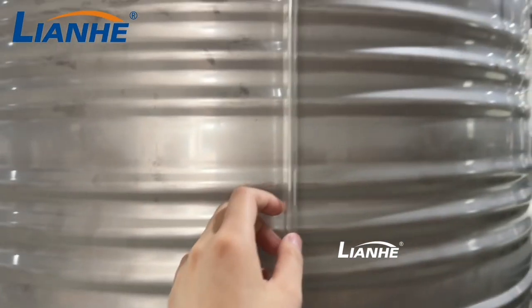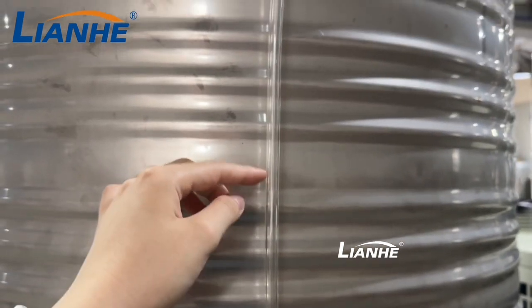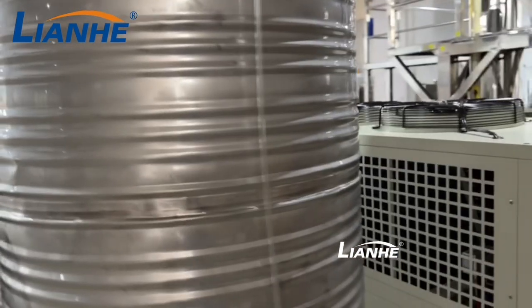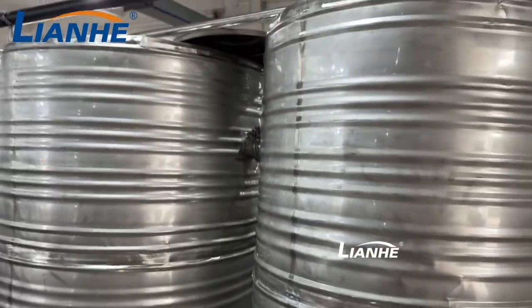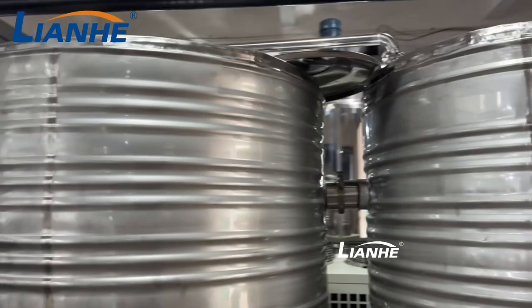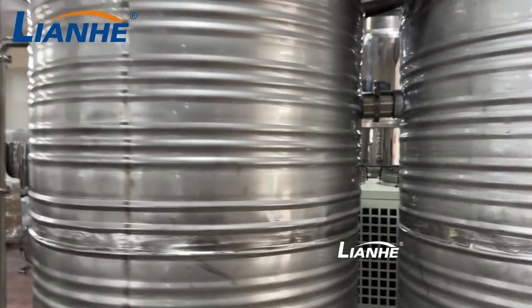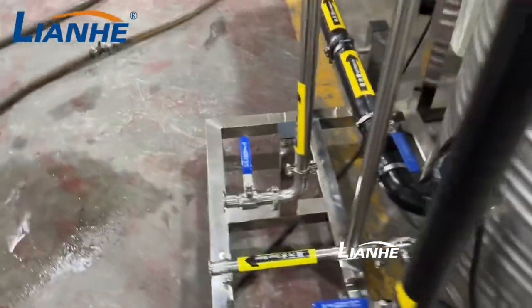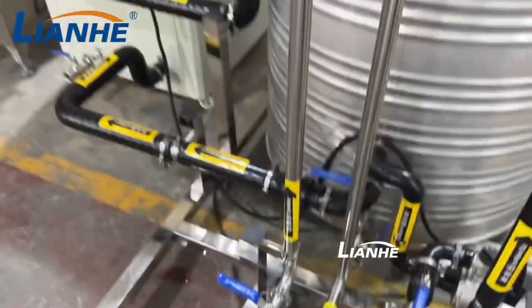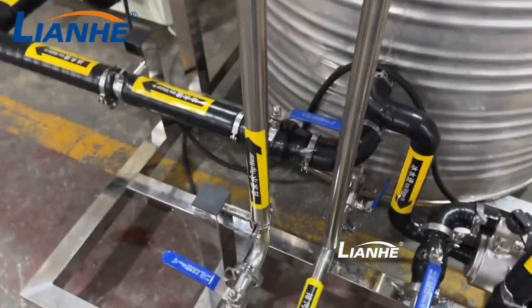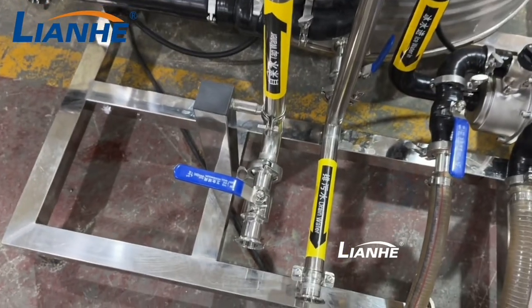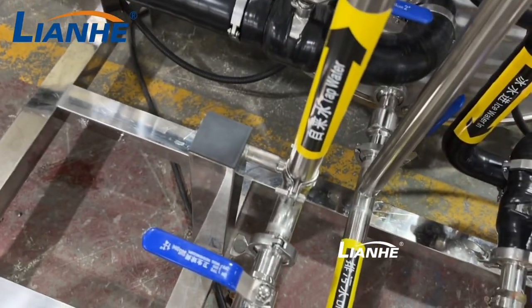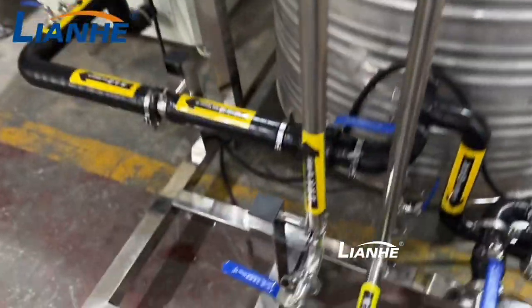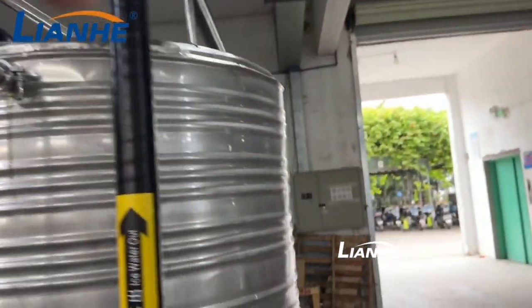And also when the water goes out here, you can use the circulation cooling function. And then we also equip you with the ball float in these 2 tanks. When the ball detects the water is full, this tap water will stop automatically. And when the ball detects the water is low, it will turn on, and the water will automatically supply into these 2 tanks.